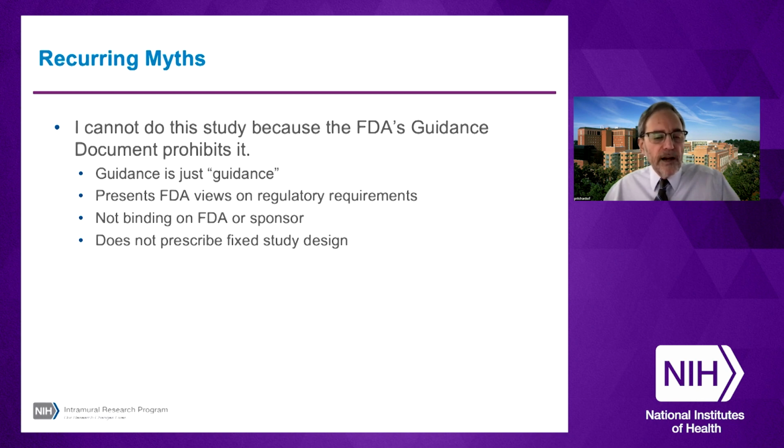If you follow the guidance to a T, the FDA doesn't have to approve your study. And if you prepare a protocol that hardly follows the guidance at all, the FDA could still approve it. It's not binding, it's just guidance. And it doesn't prescribe a fixed study design. Now, all of that said, if you're developing a study and there's relevant guidance that talks about that kind of product or that kind of disease, you would be well advised to review the guidance and follow it to the extent that you can.